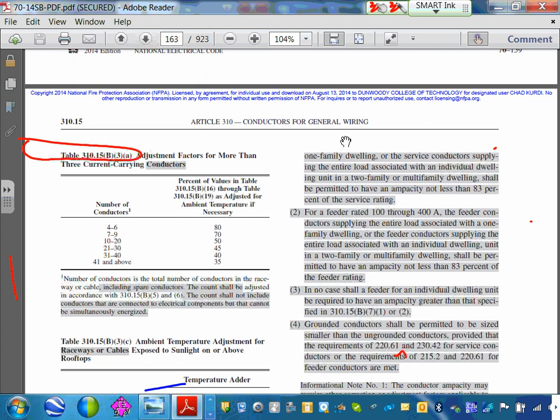Let's use these for branch circuits. You'd be a fool to use it for feeders. I mean, imagine having two feeders in one conduit. Can you do it? Yes. Should you do it? Definitely not. We group branch circuits only for receptacles and light bulbs. Even a branch circuit that goes to equipment, a good engineering design will have a dedicated pipe going to it.